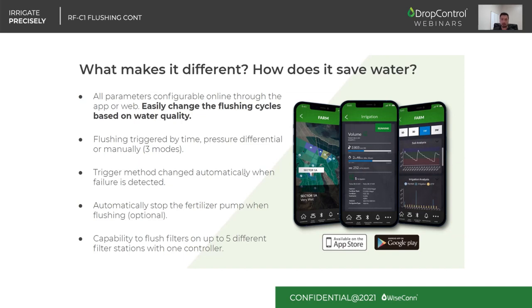So we have heard from multiple growers that one of the main complaints about actual solutions with the flushing is that any time the pressure differential switch gets bad, the system will be flushing continuously. And if no one goes to the field, they won't notice it and they won't be able to take corrective action. The main idea on our system or our controller is that you can set up a parameter that allows you to decide how many continuous cycles will need to run before we trigger the safety feature. Meaning, for example, that you can say if my flushing has run 3 times due to my pressure readings, then I want to stop flushing and only run by time or manually, because that's a high indicator that my sensor is not working properly.